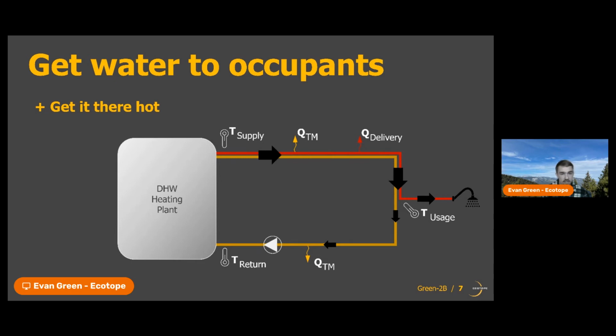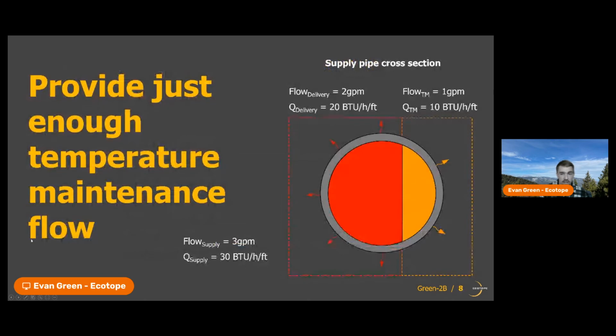And because of these two functions that this heating plant's serving, we will have two forms of heat loss. We're going to have the delivery heat loss, which is the cooling of the water as it reaches the fixture. And then we're going to have this temperature maintenance heat loss, which is the cooling of the water that's continuously circulated throughout that loop and being returned back to the heating plant. So let's look at how these two types of heat loss and these two delivery flows interact.